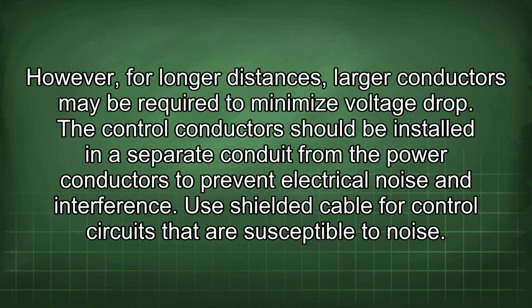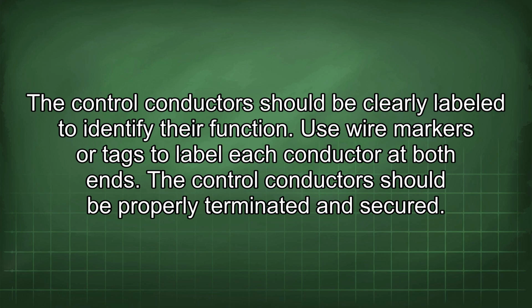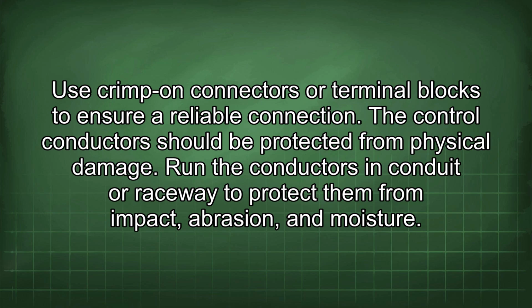The control conductor should be installed in a separate conduit from the power conductors to prevent electrical noise and interference. Use shielded cable for control circuits that are susceptible to noise. The control conductors should be clearly labeled to identify their function. Use wire markers or tags to label each conductor at both ends. The control conductors should be properly terminated and secured. Use crimp-on connectors or terminal blocks to ensure a reliable connection. The control conductors should be protected from physical damage. Run the conductors in conduit or raceway to protect them from impact, abrasion, and moisture.